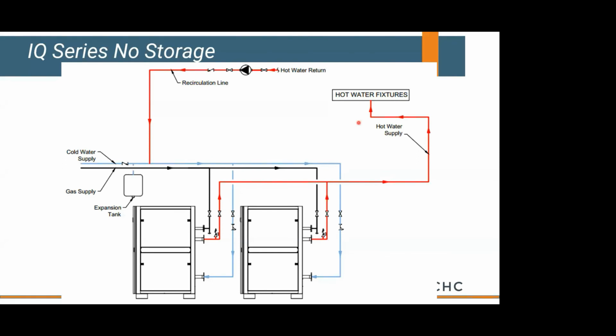Let's talk about how you might want to pipe a tankless water heater. Notice there's no storage tanks in here. We've got cold water coming into this heater on the left first, and then it continues on to the heater on the right second. Okay, and then heads out to the system. That's it. We may have a tempering valve, master mixing valve in the system if you want to add that.